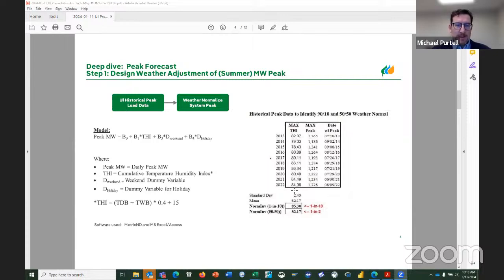So in this table, we see we've got 10 years of peak inducing summer weather temps. And to calculate the design condition, we use the norm inverse function. Probability of occurrence at 10% here is 85.3. So we're going to take the actual temperature that occurred on the peak day of the most recent summer. We're going to use this regression model to calculate the weather response, essentially the megawatts per THI. We're going to isolate weekend and holiday impacts with dummy variables. And we're going to use that adjustment to calculate the difference between the actual THI and the design THI times whatever the weather response. So we do this each year at the end of each summer.